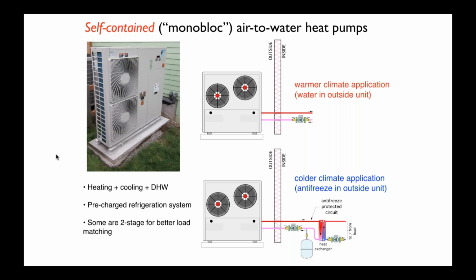That refrigerant's already there. In a warm climate, in Southern Europe, for example, in Italy, they will just run the water directly outside. Now, in Canada, that's not going to be a good idea. It would be fine as long as the heat pump is operating, but if you had a power failure during sub-freezing weather, or if the heat pump has some kind of a service issue and it's very cold out, obviously that water is going to freeze and cause some damage. So most of the systems that we're going to get into in part 2, most of them will use antifreeze if it's a monoblock heat pump. And you can either run the entire hydronic system on antifreeze, or you could put in a generously sized heat exchanger and just run a short circuit between that heat exchanger and the heat pump, and then have water on the other side. Making that decision, really, it depends on cost.